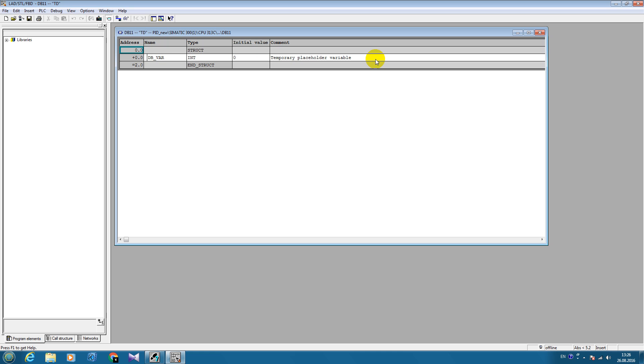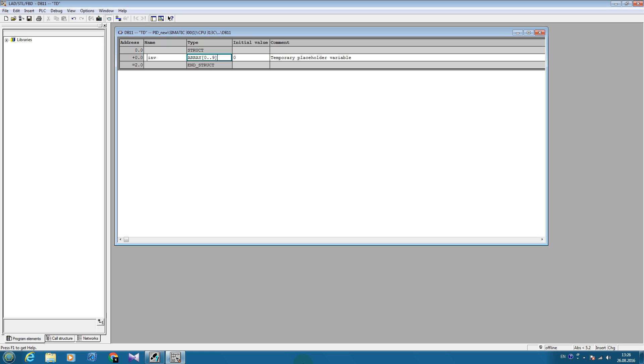To use our transport delay, we have to create new array. If I want my delay to be, for example, 1 second, I will create an array with 10 elements. If we multiply by our cycle time, 10 multiplied by 0.1 will be 1 second.